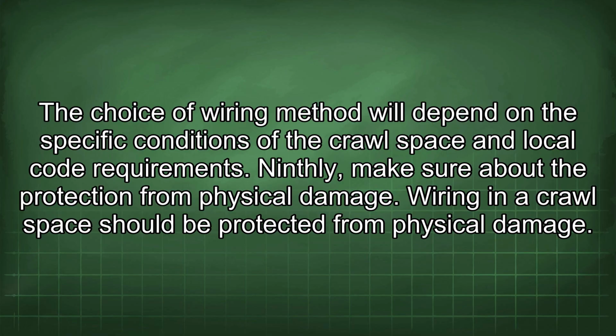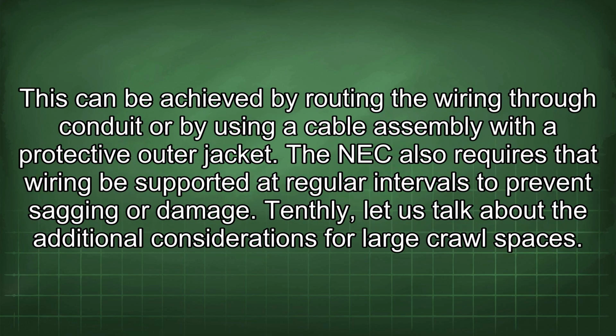Ninthly, make sure about the protection from physical damage. Wiring in a crawl space should be protected from physical damage. This can be achieved by routing the wiring through conduit or by using a cable assembly with a protective outer jacket. The NEC also requires that wiring be supported at regular intervals to prevent sagging or damage.